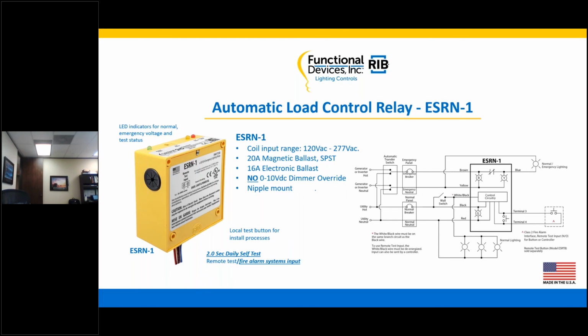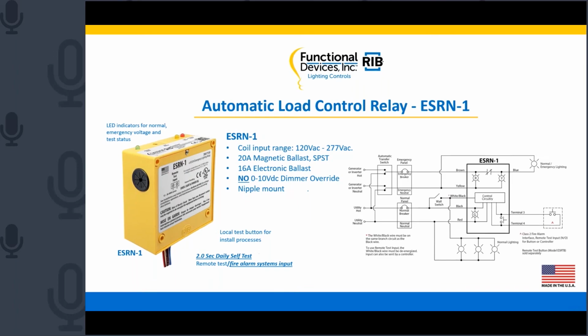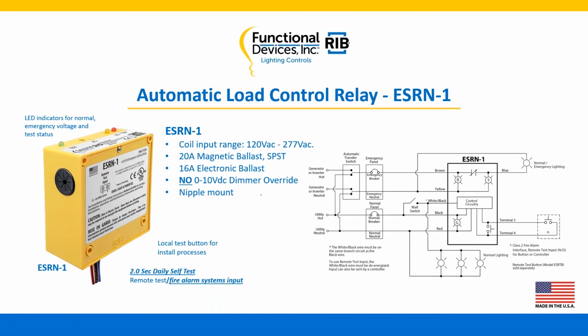We're providing the path to get to the emergency light. We give you the test button. We give you the 2-second daily self-test. And I should explain that self-test. Basically, what happens is at the end of the day, take a classroom, for example, the teacher shuts her lights off. That one emergency light will stay on for 2 seconds. The reason for that is we're providing that information so every day they know that the emergency circuit's ready, available when needed. For 2 seconds, it's on, and then it will go off. In a real situation where you lost normal power, that emergency light's going to be on at all times until normal power resumes.